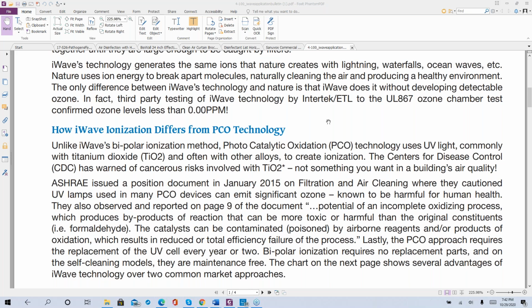And that is also where the quad metallic sheath as a catalyst over the UVC lights creates oxides, peroxides, superoxides that do similar work as the needlepoint bipolar ionization. However, some studies suggested that over time, as that metallic sheath was exposed to hours and hours and hours of UV light, there was a slight change in the molecular structure, and some ozone was produced. It was cleared by underwriters, brand new out of the box, but over time, my own personal thought was not to do this type of technology, go UV light direct, or go with the iWave.